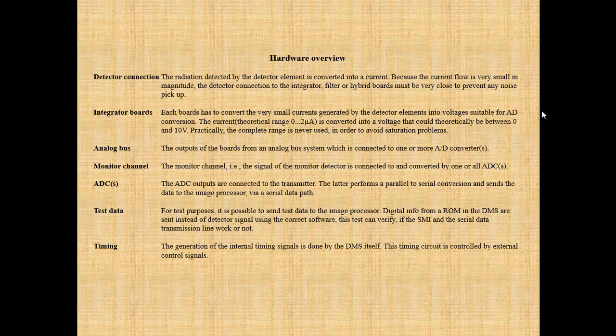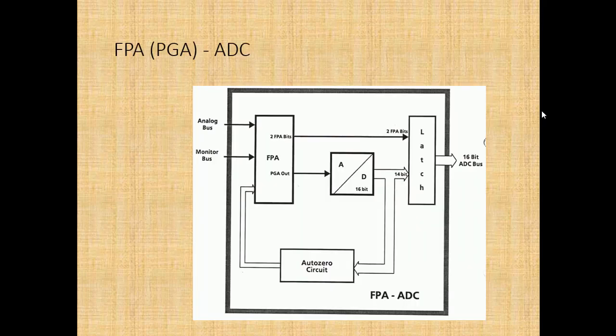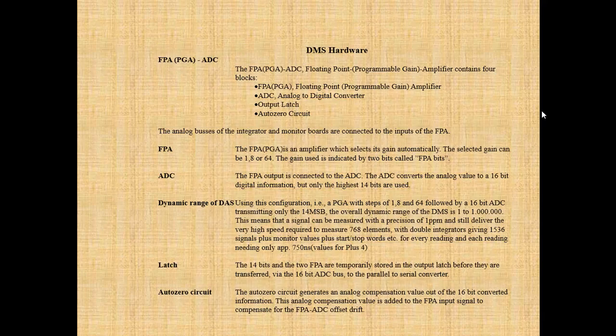Timing: the generation of internal timing signals is done by the DMS itself, controlled by external control signals. DMS hardware — FPA/PGA/ADC: the FPA (floating point amplifier) / PGA (programmable gain amplifier) / ADC (analog-to-digital converter) module contains 4 blocks: FPA/PGA, ADC, output latch, and AutoZero circuit. The analog buses of the integrator and monitor boards are connected to the inputs of the FPA.